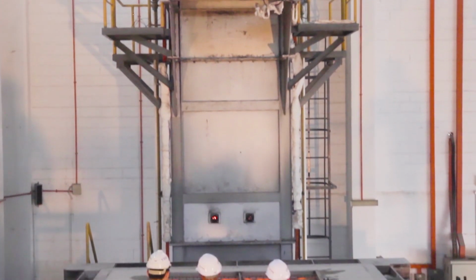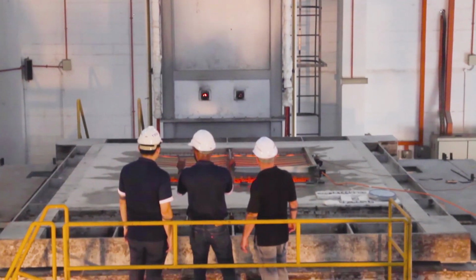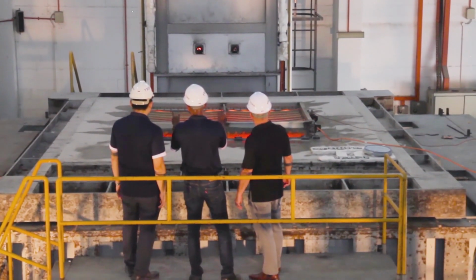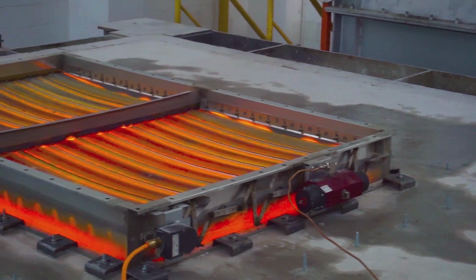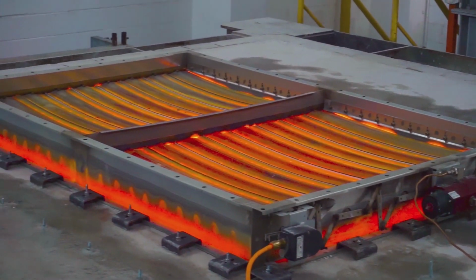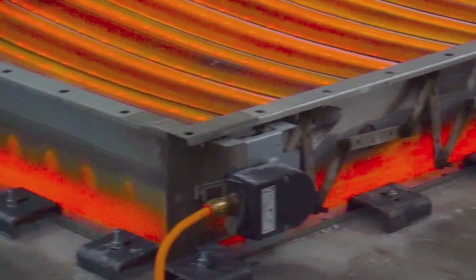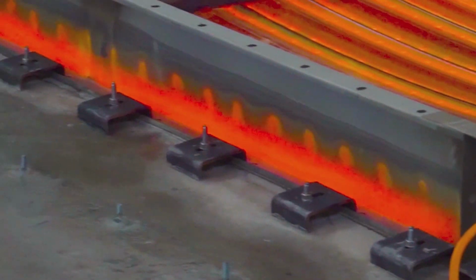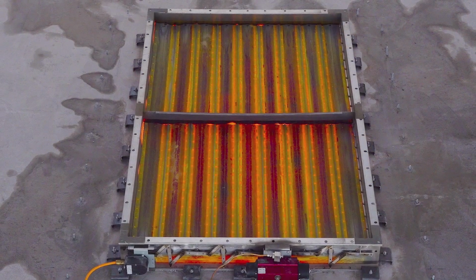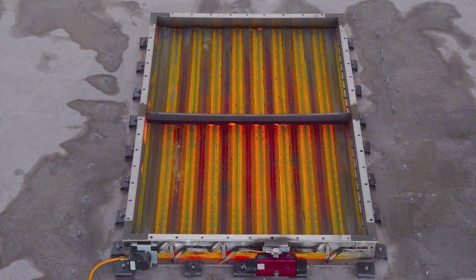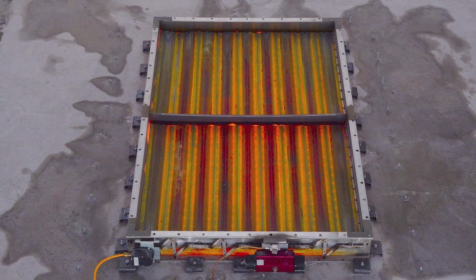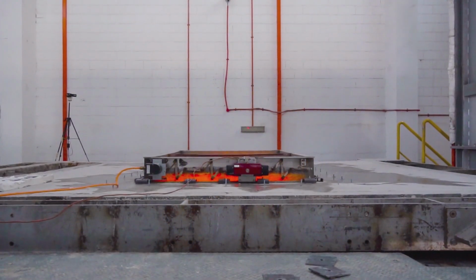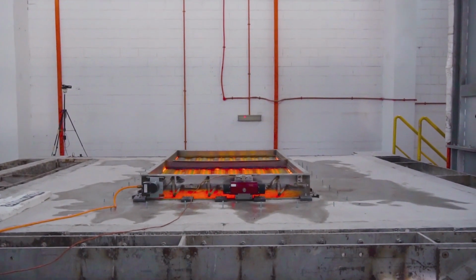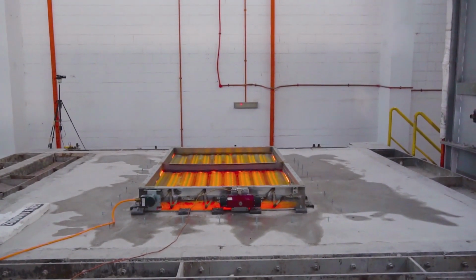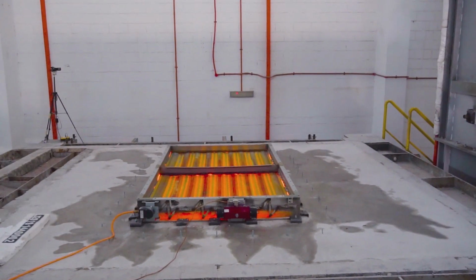To ensure that this high level of performance is maintained after the installation of the damper, the blade landing angles are not welded in place but are bolted. This enables the landing angle position to be adjusted on site to compensate for any twisting of the damper case caused by an uneven structural opening. The life-saving performance of the TROX JFM fire damper is therefore assured under all such conditions.